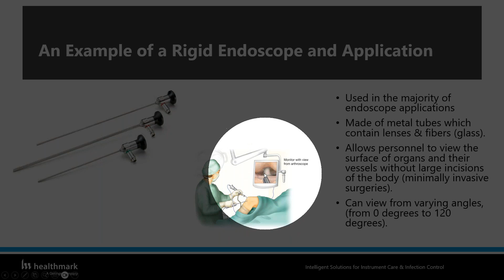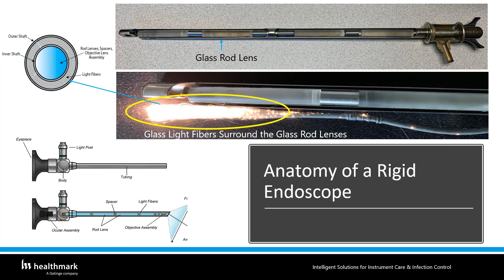And this is, again, looking under the hood. For this, you see the glass rod in here, and then you have the fiber optic glasses going basically around it. Over time, they start breaking, and the intensity of the light is not good. One way of looking at that: if you have 20% of the fibers damaged, usually the light is not really as bright as it's supposed to be.